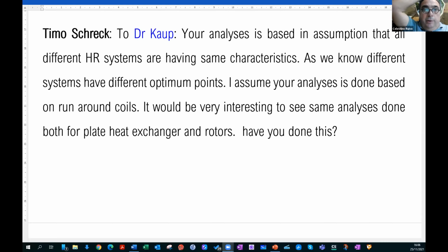Your analysis is based on the assumption that all different heat recovery systems have the same characteristics. As we know, different systems have different optimum points. I assume your analysis is done based on run-around coils. It will be very interesting to see the same analysis done for both plate heat exchangers and rotors.